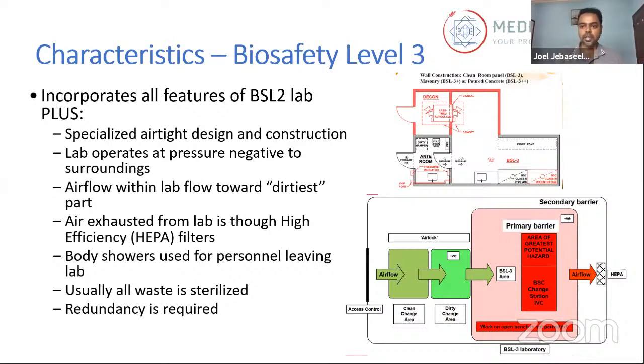All air that goes out of BSL level 3 must be decontaminated. So it must go through HEPA filters, and there are always redundant systems to ensure that if one HEPA filter fails, there's a second redundant HEPA filter. There'll always be airlocks, and you typically need to work in pairs. In a lab like BSL level 3, you're not supposed to work alone. You always need a second person working with you, because if there's a spill or someone is having a heart attack or something like that, you need the second person to manage that risk. So you cannot work alone in a BSL level 3.